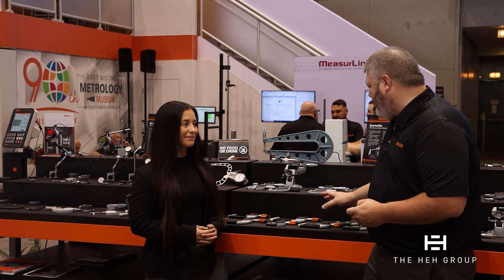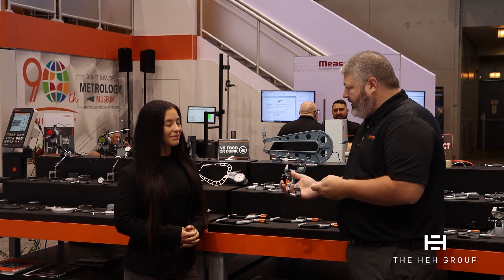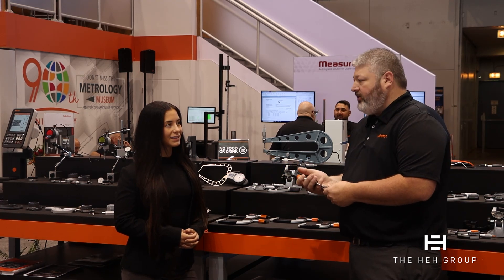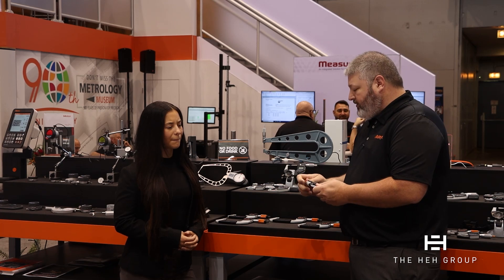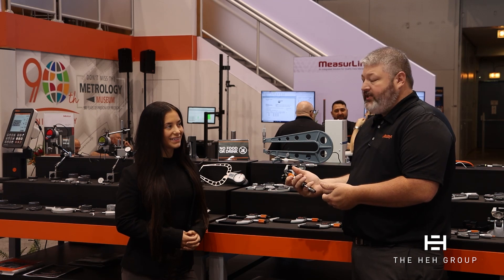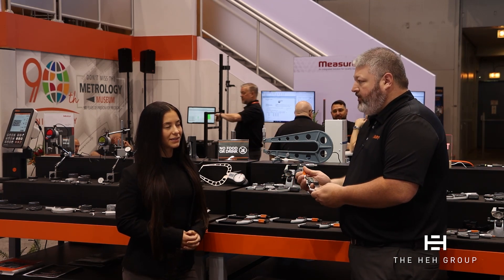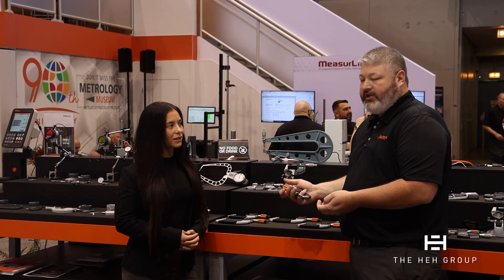So right here are our quantum mics. This is our zero to one quantum mic. We have the older quantum mics — they're about five years old. The main difference between a regular micrometer and a quantum mic is the pitch of the thread. Everyone knows there's a thread inside the spindle that drives the spindle back and forth, and that determines not only the accuracy but also the speed. The quantum mic actually has a two millimeter thread pitch, which allows us to move four times faster than traditional micrometers.